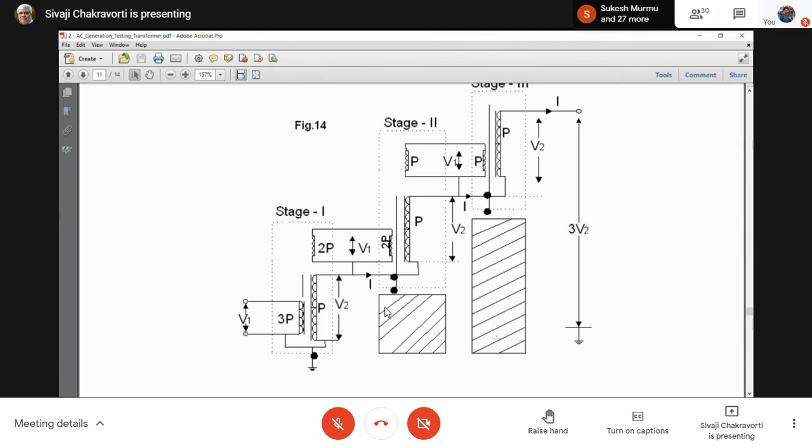This lower terminal and the tank, which means that the second one, the tank will be at a potential of 250 kV. Now the issue is, then you cannot put it on earth. That means you have to make an insulating structure and put the transformer on it.